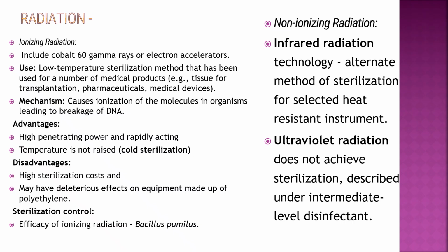Advantage: high penetrating power and rapidly acting. Temperature is not raised, so it is also called cold sterilization. Disadvantage: high sterilization cost and may have a deleterious effect on equipment made of polyethylene. Sterilization control: efficacy of ionizing radiation is checked by Bacillus pumilus.